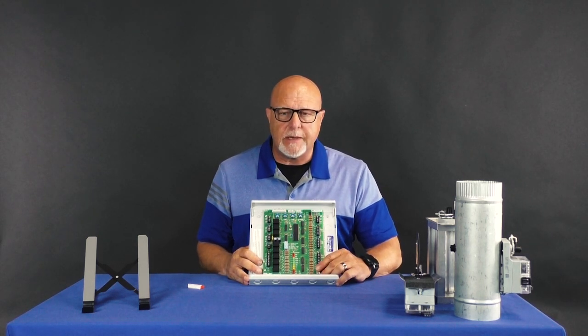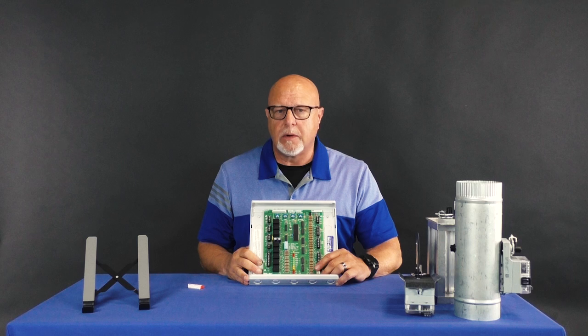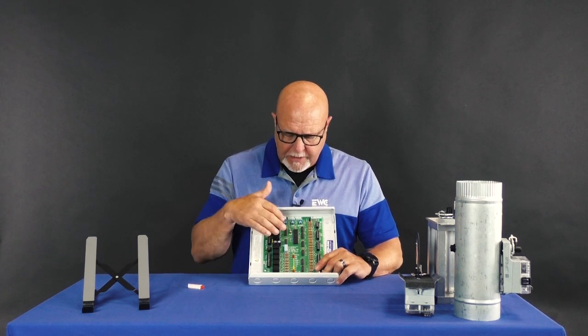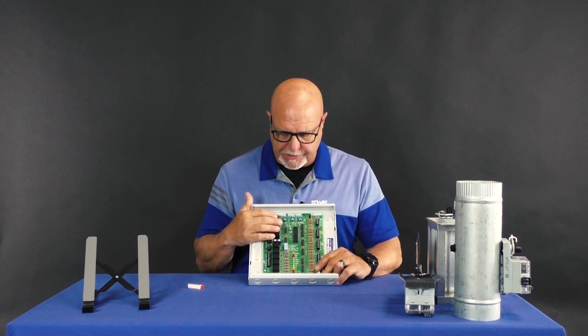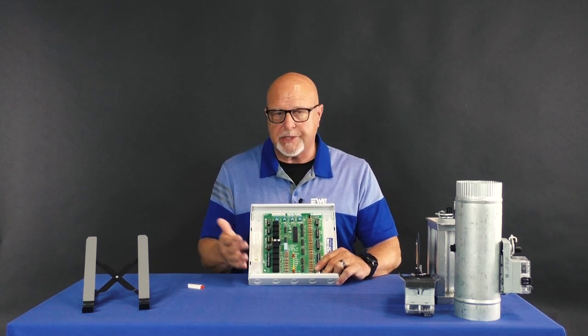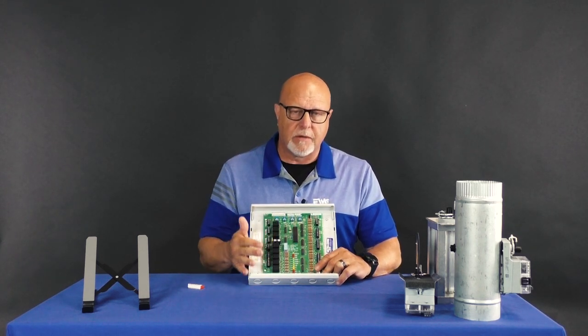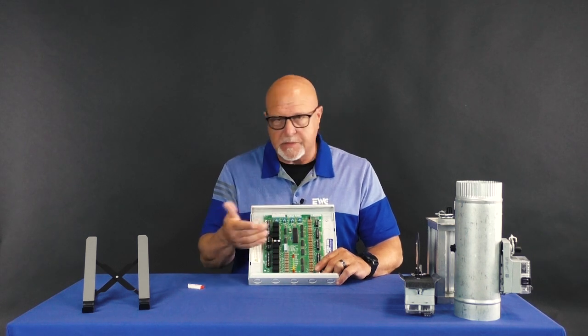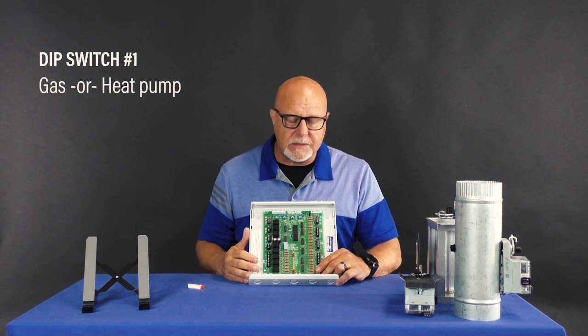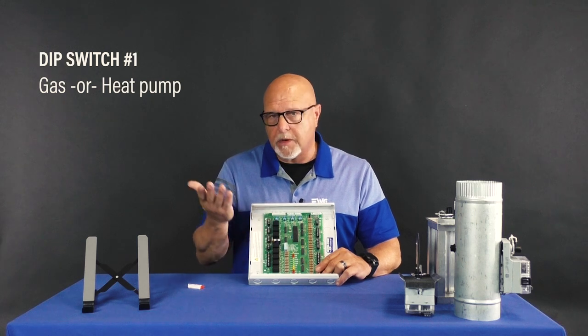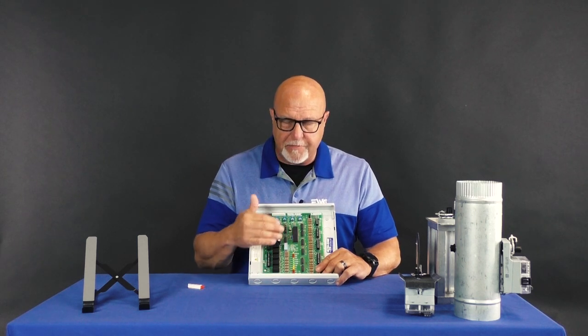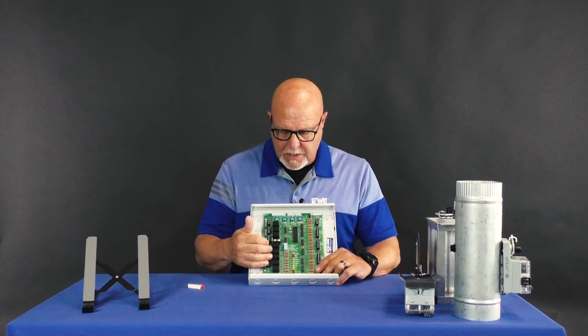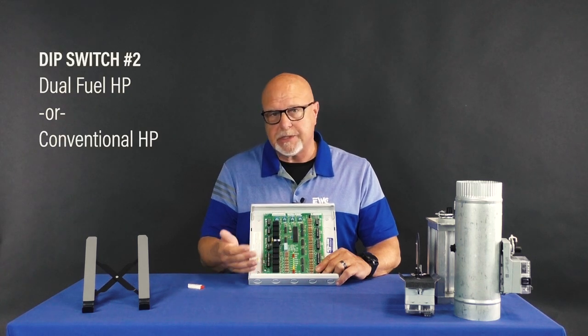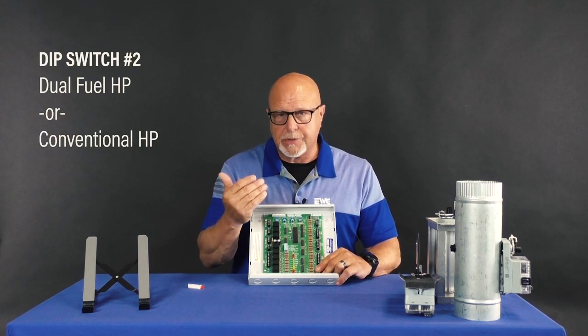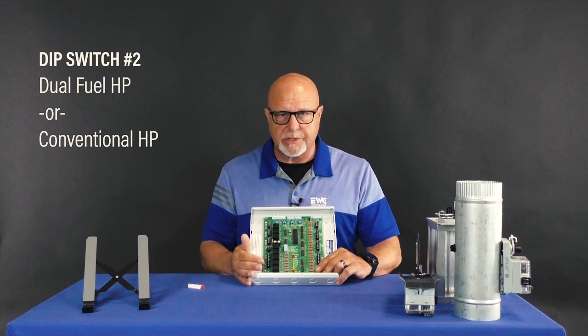Very simple. It is a dip switch oriented board, only 8 dip switches to help you set up this board. Very quickly I will go through these dip switches, and the first one is, what is your system? Is it a heat pump or is it something other, like a gas furnace? You'll move the dip switch to the right for a gas and left for a heat pump. If your system is a heat pump, the second dip switch asks you, is it a dual fuel heat pump or is it a traditional conventional style heat pump?